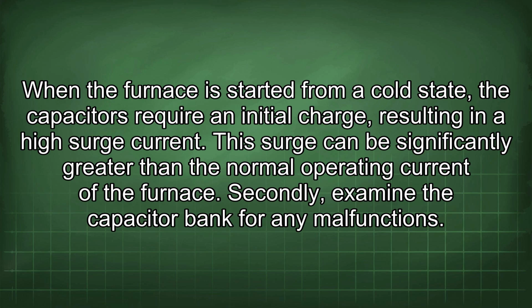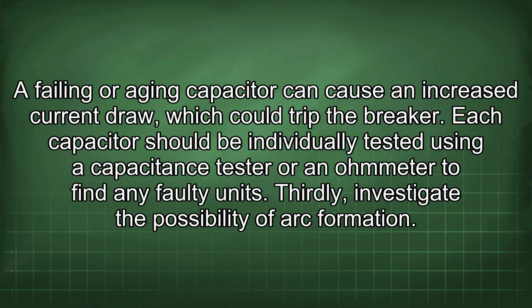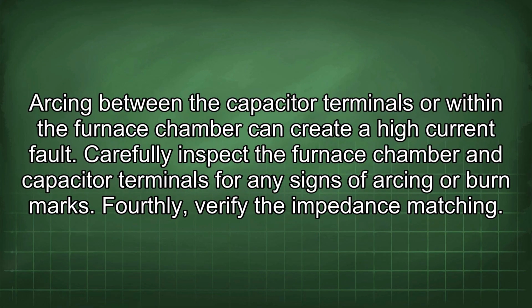Secondly, examine the capacitor bank for any malfunctions. A failing or aging capacitor can cause an increased current draw, which could trip the breaker. Each capacitor should be individually tested using a capacitance tester or an ohmmeter to find any faulty units. Thirdly, investigate the possibility of arc formation. Arcing between the capacitor terminals or within the furnace chamber can create a high current fault. Carefully inspect the furnace chamber and capacitor terminals for any signs of arcing or burn marks.